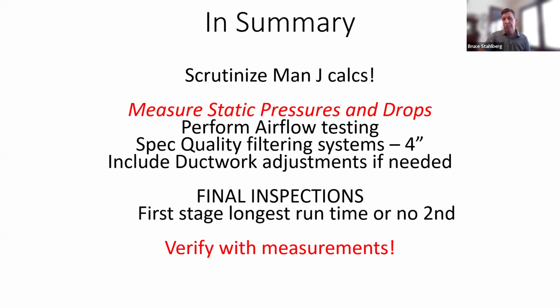So first of all, when you get a manual J calculation from a contractor, it's okay to scrutinize those. They often do not measure things. I've had them out to my house before. They don't measure, they don't look in the attic, they kind of go by rule of thumb. So that's okay for you to scrutinize those. I can kind of safely say that if it's a Rambler, the furnace could be 40,000 BTUs, probably a 1.5 ton air conditioner. Those are kind of rules, but we often see them much larger than that.